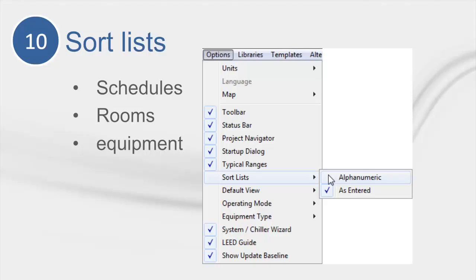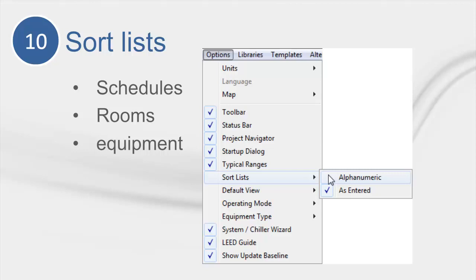For tip number 10, trace normally displays inputs in the order they were created. Most people seem to be more comfortable with dropdowns providing information in alphanumeric order. To change this, you will need to travel to the Options, Sort Lists, Alphanumeric Selection. Additionally, when you are importing library members, or if you are creating library members, remember that you need to let trace refresh before you can select the library members. For instance, if you are in the Internal Loads tab and decide to make a people schedule, after you create it in the library, you will need to refresh the Internal Loads tab. You can do this by clicking off the current tab, onto another, and then coming back to the Internal Loads tab. Then, your library member will be selectable in the dropdown. Do not click the Actions Refresh Library values. This is something very different and will convert overwritten values in the project to library values. It is not reversible, so be careful if you decide to use it.